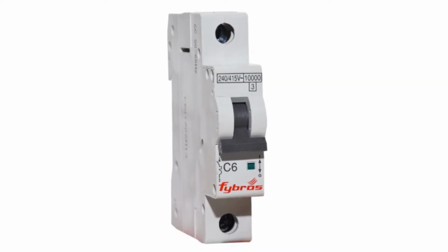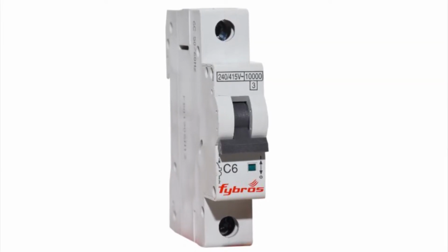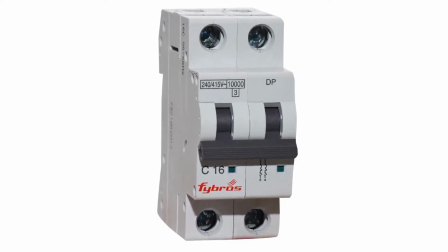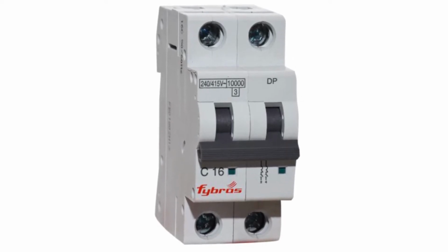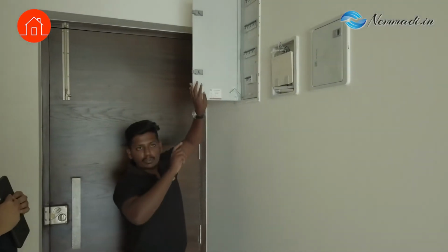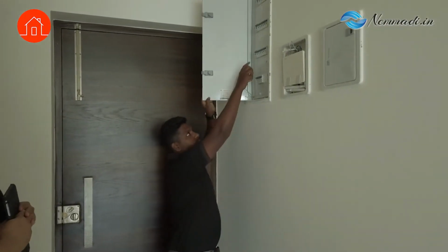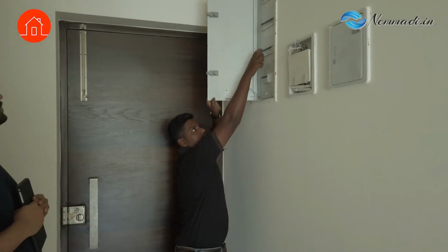And also there are two things. One is the lighting circuit, which caters to the lights, which is called the 6 amp circuit. And another one is the 16 amp circuit. 16 amps is a higher current rating used for the geysers, the stoves, and the higher wattage equipment. So there are different circuits. All the circuits get divided in the main distribution board. So you will have different circuit breakers to control each circuit.